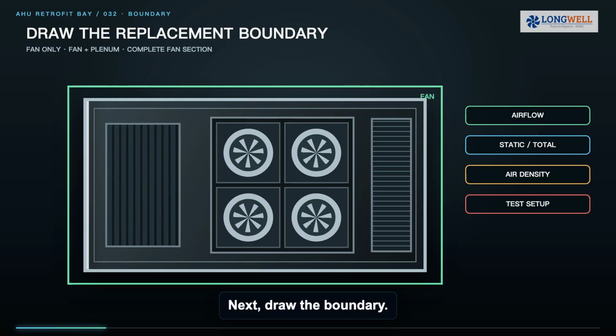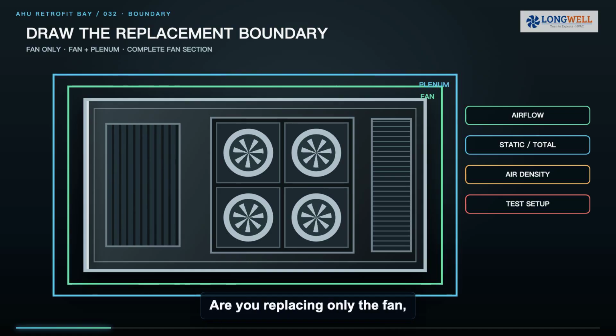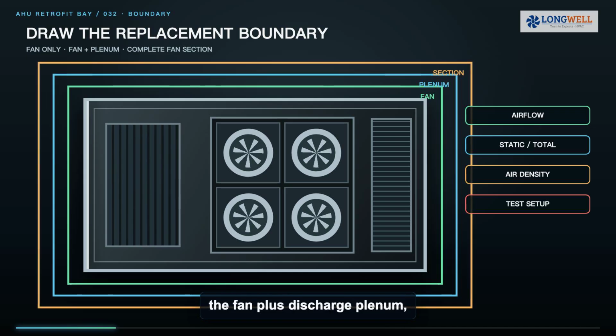Next, draw the boundary. Are you replacing only the fan, the fan plus discharge plenum, or the complete fan section? Do not compare a catalog free air maximum with installed static pressure. Keep airflow, pressure type, air density, and test arrangement on the same basis.